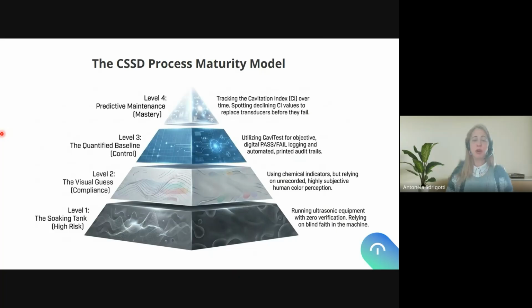So the CSSD process maturity model is what we are trying to offer to the market, okay, where, specifically for ultrasonic washers, we have level 1, which is the soaking tank, high risk. We are running ultrasonic equipment with zero verification, relying on blind faith in the machine. We just hear it's working, but we don't know actually if all transducers are working and if the cavitation energy is necessary to clean our instruments. Then we can jump to level 2, the visual guess, which is compliance. We are compliant, but we are using chemical indicators, only relying on unrecorded, highly subjective human color perception. If we jump to level 3, which is the one we are offering nowadays with this webinar with the Bionova CaviTest, we have the quantified baseline.